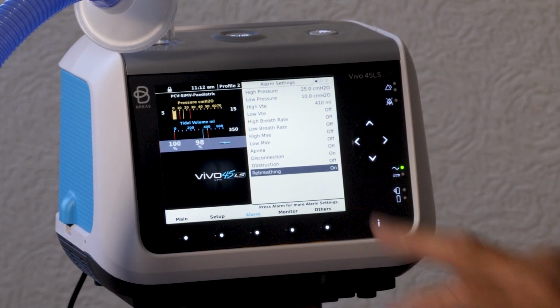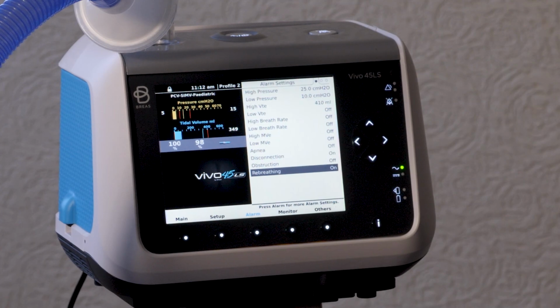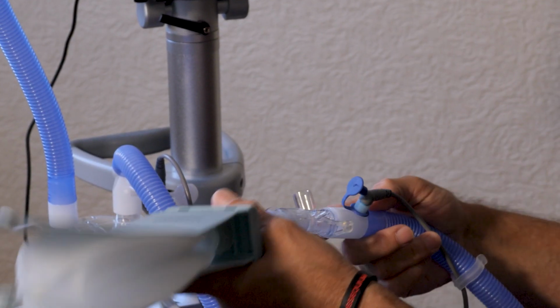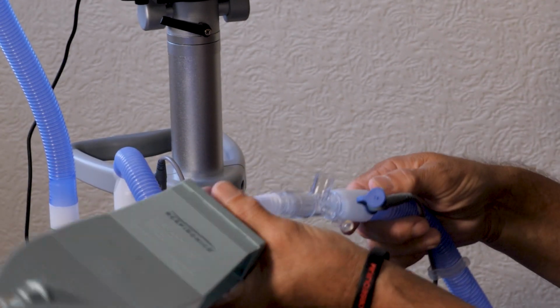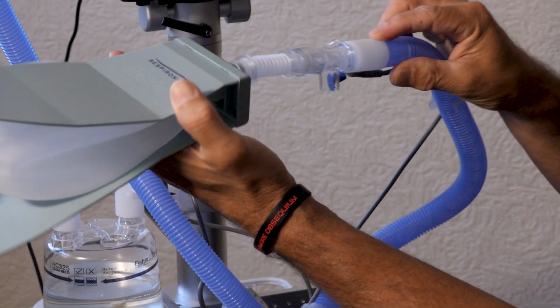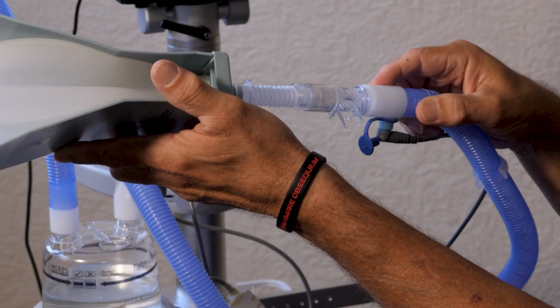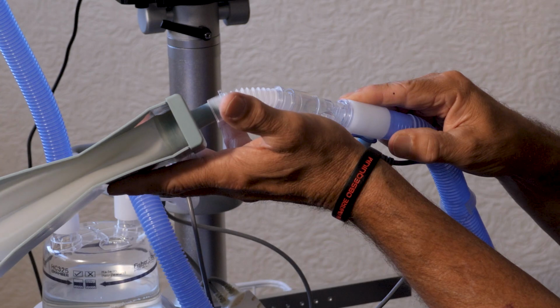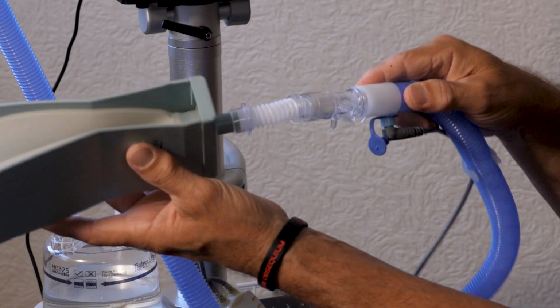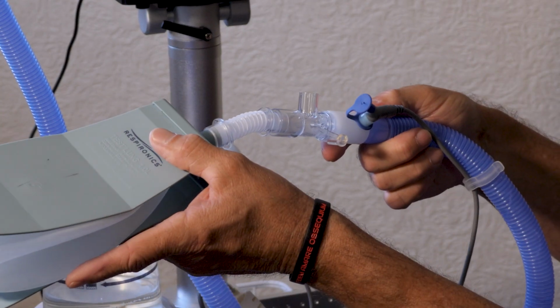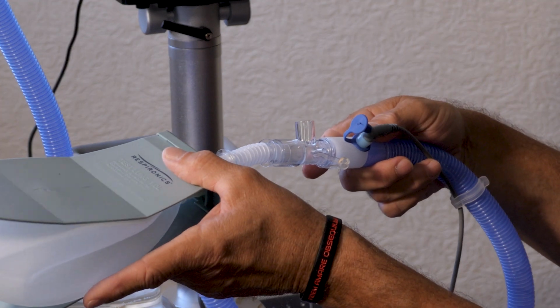The last alarm I want to talk about is your rebreathing alarm. Your rebreathing alarm is basically a low circuit leak alarm. It means that you're not getting rid of enough exhalation. And in this particular circuit, you have an exhalation valve that's right here. If you're using this exhalation valve, you don't want to have it in a position where it's pointed downward like this, or being onto the clothing or the bedding of the patient. You want to have it so it's either like this or like this, so that it's freely moving air out.